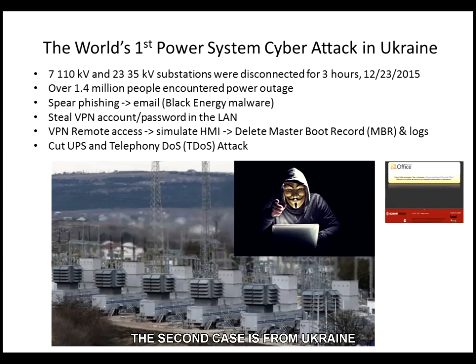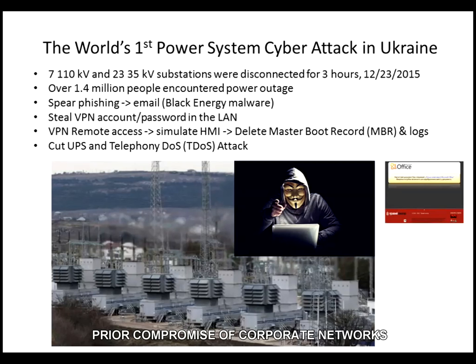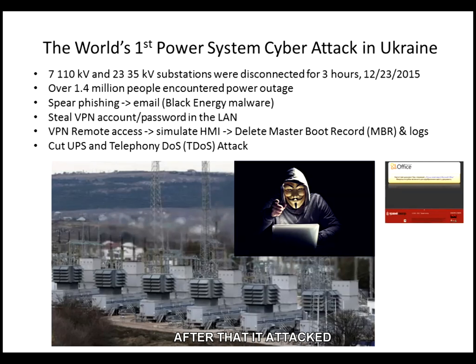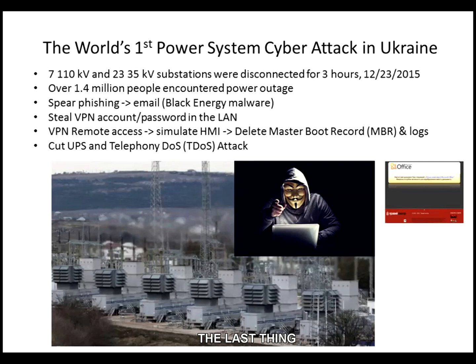The second case is from Ukraine, where a cyber attack on the power system caused over 1.4 million people to experience a power outage for three hours. The attack was complex: it began with compromising corporate networks using spear-phishing emails with BlackEnergy malware, then seized SCADA control to remotely switch substations off. It then disabled or destroyed infrastructure components, corrupted files on servers and workstations with KillDisk malware, and used a denial-of-service attack on the call center to deny consumers up-to-date information about the blackout.